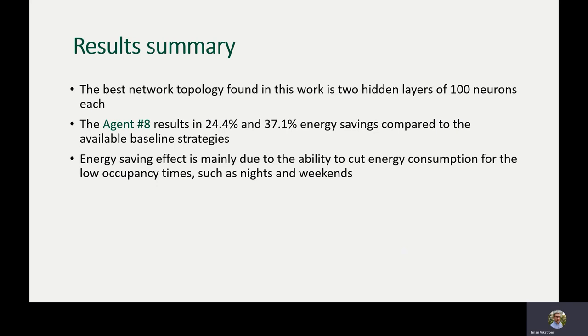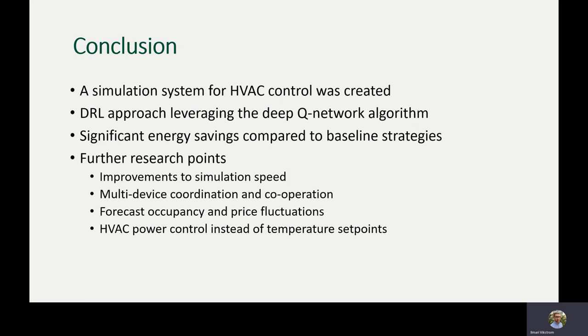The best network topology found in this work is two hidden layers of 100 neurons each. Agent number eight was able to achieve significant energy savings compared to the available baseline strategies, and this energy-saving effect is mainly due to the agent's ability to cut energy costs when the occupancy trend is low. In conclusion, a simulation system for HVAC control was created in this work. Using this system, a deep reinforcement learning approach leveraging the Deep Q-Network algorithm was constructed, and the best agent was able to reduce energy consumption significantly relative to two different baseline strategies.